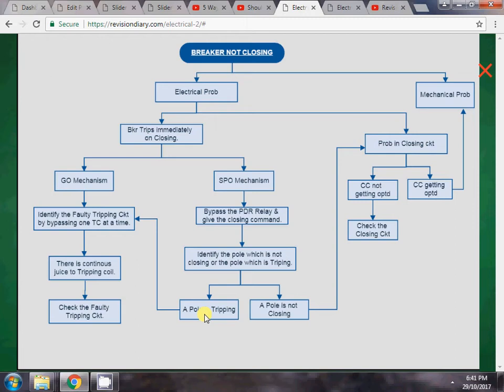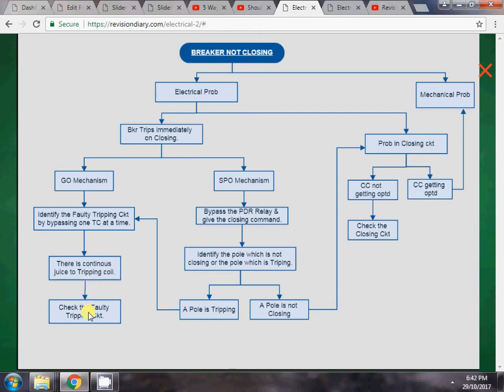If, for example, the R phase pole is tripping, we have to identify the faulty tripping circuit by bypassing one trip circuit at a time. There are two tripping coils in the tripping circuit. We bypass one tripping circuit, keep trip coil 2 in service, and give the closing command. If the breaker then closes, the bypassed tripping coil is faulty or is receiving a continuous signal. We then check that faulty tripping circuit.